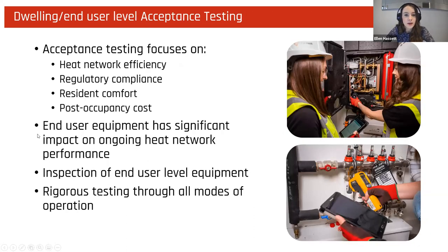So from a dwelling perspective, acceptance testing is designed to focus on four key areas throughout the process: heat network efficiency, regulatory compliance, resident comfort, and post-occupancy cost. A set of commissioning parameters and installation benchmarks are set early in the process for commissioning engineers to work towards. Initial acceptance testing is first carried out, ideally as soon as the first 10 to 20 dwellings are commissioned, to prevent the escalation of systemic issues in commissioning. The end user equipment is then tested and checked to verify dwelling performance by inspecting for installation issues and faults, and then carrying out rigorous testing in all three modes of operation: standby, domestic hot water, and space heating.